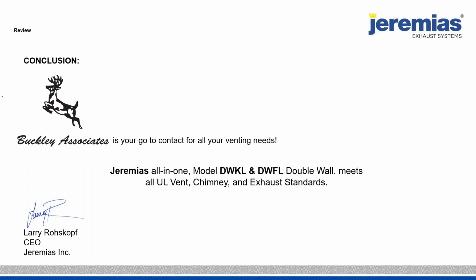Okay, the one last question I had is you talked about fume hoods. So it sounds like it could be used for perchloric acid, but I mean, those ducts typically require sprinklers in the ducts. Can your system accommodate that? Yes, we have standard nipples we put on for the sprinkler systems. Typically, they're a 1-inch nipple, but they can be whatever is required. We do that also for like the city of Las Vegas on their grease duct systems. They put a fire sprinkler every 10 feet. That's pretty common. Okay, great. Thank you. Oh, thank you.